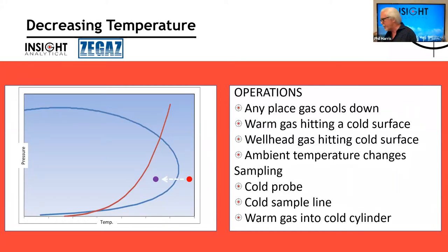Another common one: if we're running through a pipe, and the pipe's outside, and we're in Canada, we have this risk that it's going to be cold outside. So that pipe gets cooled off. So it may be that in the processing facility, we're in the plant, and our temperatures are high enough that everything is gas phase. As it cools off, as soon as we cross here, we hit a hydrocarbon dew point, cool it off more, we hit a water dew point. And so both of those are problematic for us. And so we're going to see in the operating facility, any place where the gas cools down. So we go through a heat exchanger, we go through a cryo system, we're going to condense out liquids.